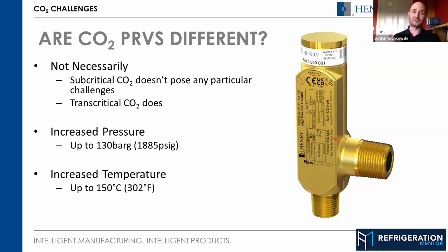Again, the other consideration from a design point of view with temperature is the spring, because if the valve is in a high temperature environment and you haven't selected the correct spring design or materials or pre-stressed it enough, it can actually lose tension due to the temperature over the life of the valve, which makes the valve open early, which obviously is something we don't want.